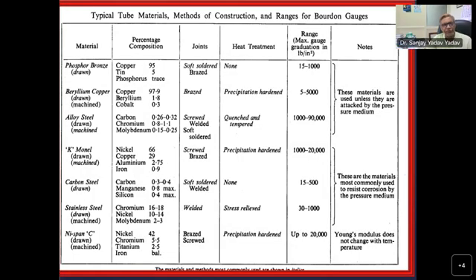When we come to the typical materials for the construction and range of Bourdon gauges, you must understand the intrinsic properties of Bourdon gauges. Phosphor bronze, beryllium copper, alloy steel, carbon steel, stainless steel, and nickel-span type are used. These are the ranges: for example, phosphor bronze gauges are used up to 1000 psi, carbon steel up to 500 psi, and others up to 20,000 psi, and you can use all these gauges.